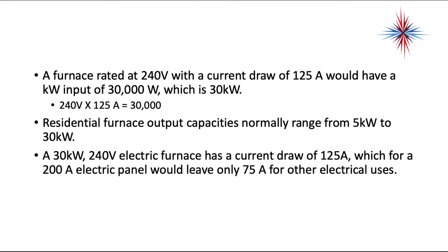A furnace rated at 240 volts with a current draw of 125 amps would have a kW input of 30,000 watts, which is 30 kW. 240 times 125 equals 30,000. Residential furnaces' output capacities normally range from 5 kW to 30 kW. A 30 kW 240 volt electric furnace has a current draw of 125 amps, which for a 200 amp electrical panel would only leave 75 amps for other electric uses.